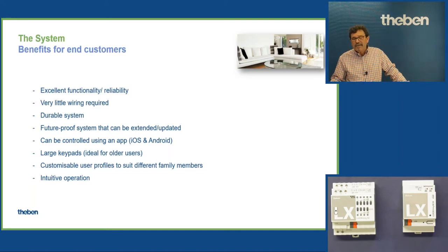Because they have doubts. So what if the power supply is disconnected, or is probably destroyed in an unexpected event? So what if now I'm sitting in the darkness? So you have to give the reasonable answer. No, you aren't. As long as you have the power 230 applied to the system, on each of these DIN rail solutions, DIN rail actuators, for instance, you can anytime manually operate on, off, dimming up and down, lower or raise the blinds, for instance, or open or close the heating, manually, you can.